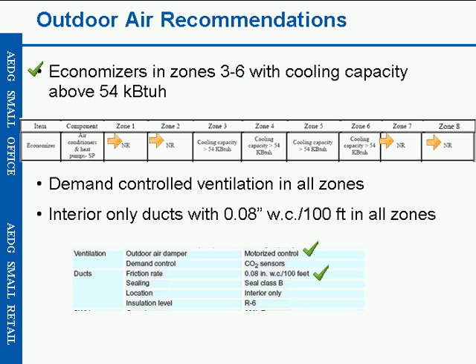As we've shown here, it is important to look at the whole system and not just the device that's providing the heating and cooling and moving that air. But we really wanted to start getting at duct design, especially in a building sector where ductwork is not usually well thought out. And so there are how-to tips on dealing with takeoffs and using gentle elbows, etc., as well as encouraging right-sizing the ductwork so that you can reduce some of your airflow rates and reduce those frictional losses along the duct.